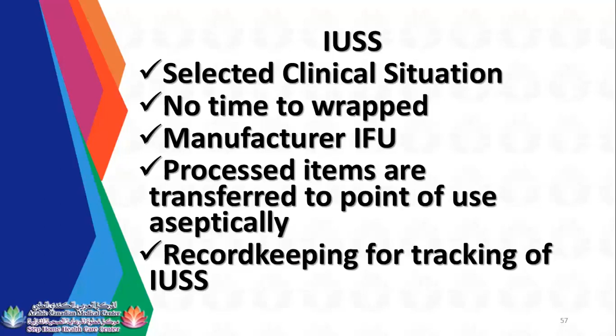The manufacturer's IFU should be followed because there are some instruments that are not allowed to be run in IUSS. Processed items are transferred to the point of use aseptically. Record keeping for tracking of IUSS means you need to track who is processing the IUSS, what the reason is, who the patient is, why they use IUSS, and what the instruments are. Implants should not be processed in IUSS unless documented as an emergency situation, a life and death situation of the patient.